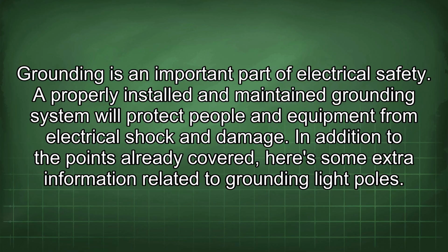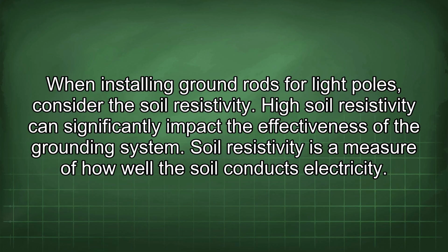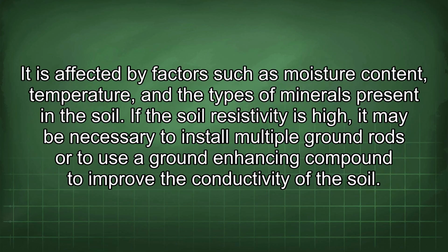In addition to the points already covered, here's some extra information related to grounding light poles. When installing ground rods for light poles, consider the soil resistivity. High soil resistivity can significantly impact the effectiveness of the grounding system. Soil resistivity is a measure of how well the soil conducts electricity. It is affected by factors such as moisture content, temperature, and the types of minerals present in the soil.